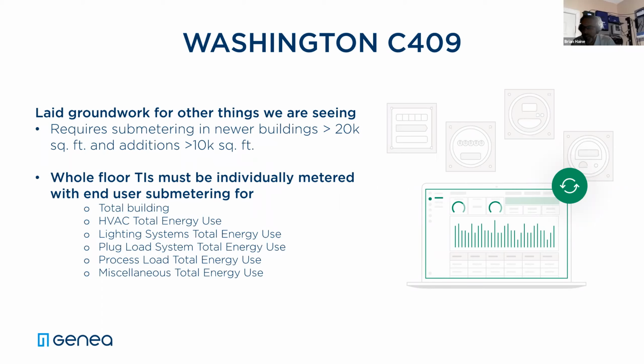The next one I want to briefly touch on is Washington State. This started off as Seattle City Code, and they've done some nice stuff there. They've done it a bit differently, focusing on different load types but also on requirements for the metering systems themselves, specifically calling out metering systems, data collection systems, data display, and system commissioning. So instead of just throwing meters on the wall where an electrician during a TI says the light came on and the smoke didn't come out, they're actually requiring certified sign-off, the same way Liz mentioned for New York. Everything has to be documented. Washington's doing some really nice stuff, in my opinion.